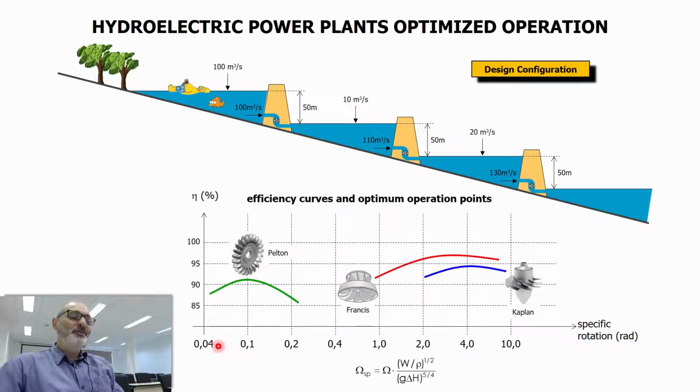And what are the types of turbines? Water turbines. There are three types: Pelton, Francis, and Kaplan. In Ibitinga, for instance, it is Kaplan. I don't know if you know, in Cubatão there's a power plant called Henry Borden. It uses Pelton turbines, for high altitudes. Delta H is very big. So the normalized specific rotation is low because delta H is high.